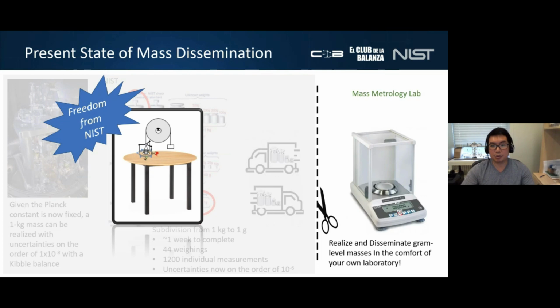So we introduced this idea of a commercial tabletop Kibble balance designed for private industry. A modernization of mass metrology such as this would take full advantage of the new SI, which severely truncates the traceability chain. You could essentially realize your gram level working standards to ppm uncertainty on one side of the lab, and then walk over to the other end and use it to calibrate your analytical balances.